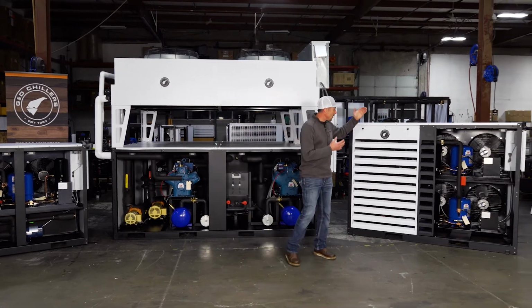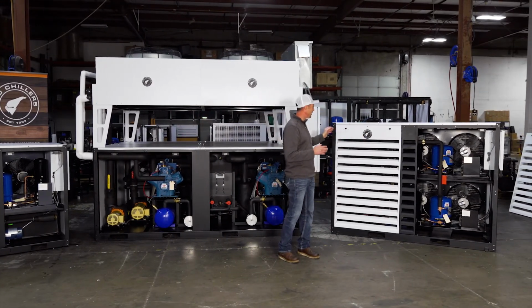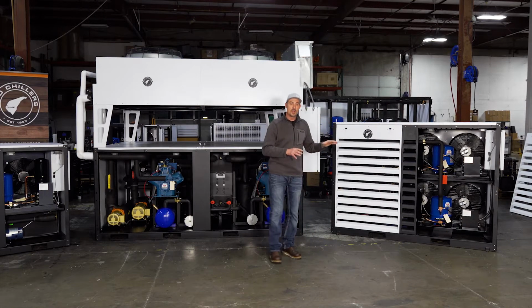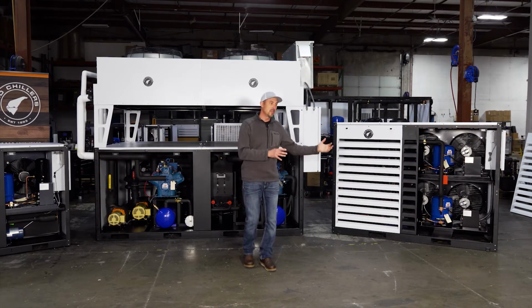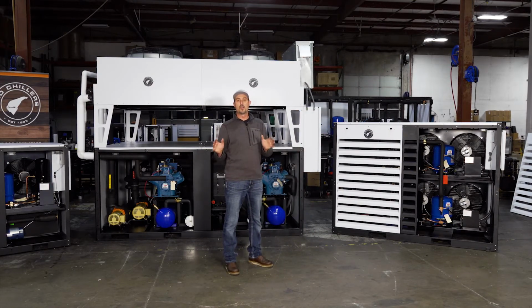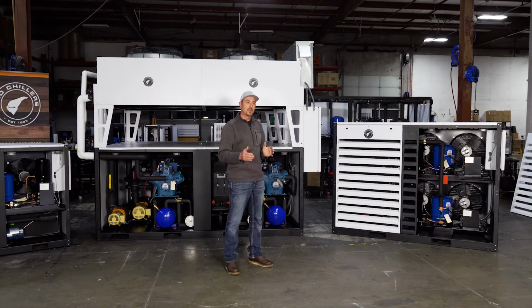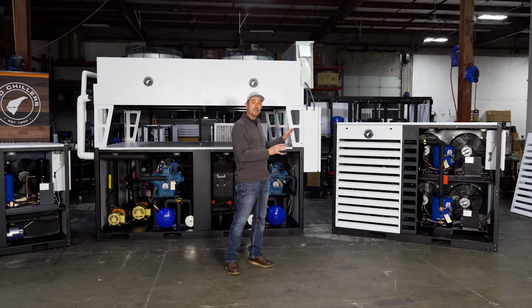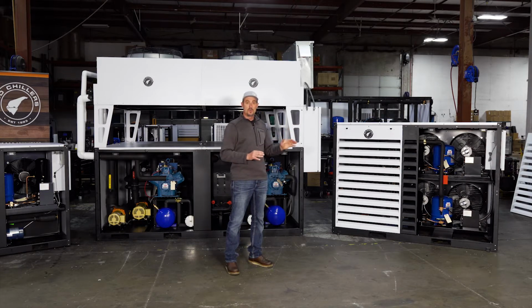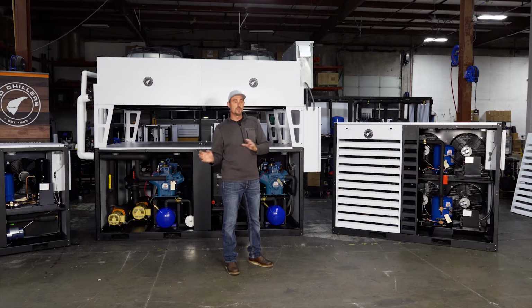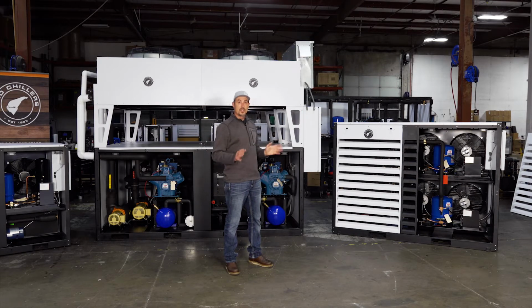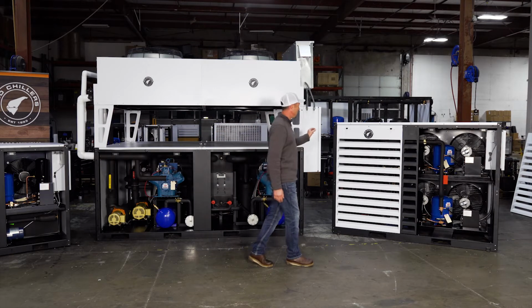Redundancy is huge, as I said. Having a chiller that's built here as a complete package, with nothing built on site, allows us to run it in our run station and completely dial it in so it's operating properly before it even leaves here. So when you get it, there's no dealing with refrigeration piping or charging the system. It's ready to go, which saves you time in the field. The other thing is quality control.